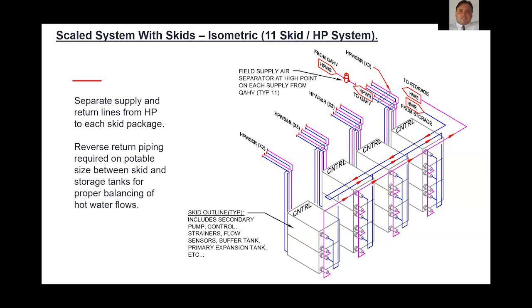So fairly compact footprint. And again, the biggest benefit here, even though this is obviously a lot of pipes to deal with on the primary side to each of the heat pumps, is that in this scenario, if you lost a specific heat pump, you've taken out less than 10% in this case of your total capacity. We're sizing these systems for these peak design day worst case scenarios, but in reality, for most operating hours, they're going to be below that. So your ability to maintain and continue operation in the building is really enhanced by taking on strategies like this under larger installations.